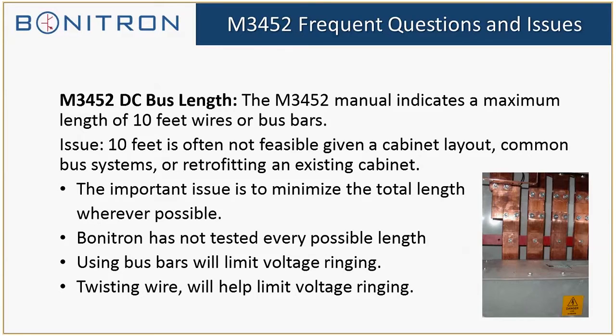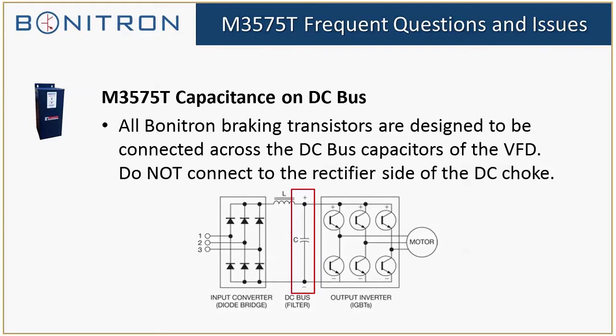So now moving on to our other braking transistor, the M3575T. This one is only powered off of the DC bus, so there's no control power coming in from the AC. It will start up once the voltage gets high enough, 20 to 50 volts on the DC bus, and the little yellow LED will come on the front once it's above 50.